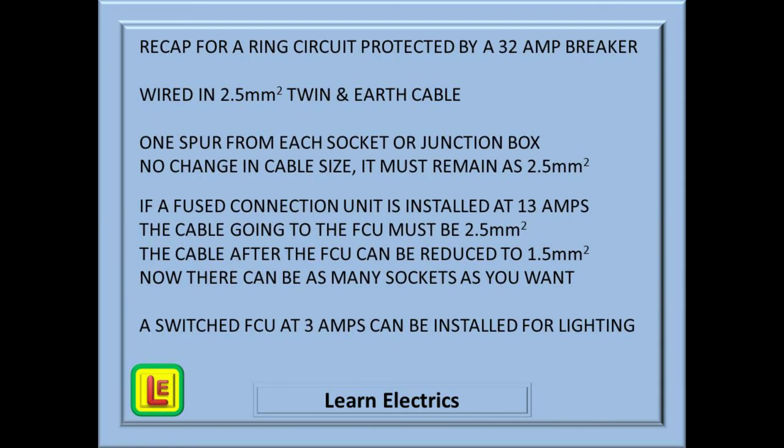That is it. It is not that difficult. Just follow some very basic rules. The main one being to protect the cable from overload. A recap then on what we have done. This is for a 32 amp ring circuit wired in 2.5mm twin and earth cable. Only one spur from each socket or junction box on the main ring. No change in cable size between the main ring and spur. It should remain at 2.5mm.